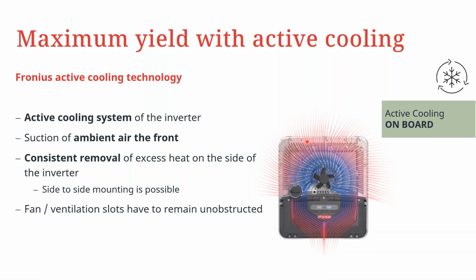The characteristic of the GEN24 is quite similar as far as cooling technology is concerned, compared to the Snap inverters that a lot of our partners and installers are familiar with. We have active cooling integrated in the GEN24 Plus. You can see that the cooling fan is centrally placed. This allows the inverter to suck cooling air from the front side of the inverter. And then you have consistent heat removal throughout the sides of the inverter. The design of the heatsink allows the hot air to come out of the inverter from all directions. This means that the cooling technology of the GEN24 is a lot more efficient than even the Snap inverters in this sense.